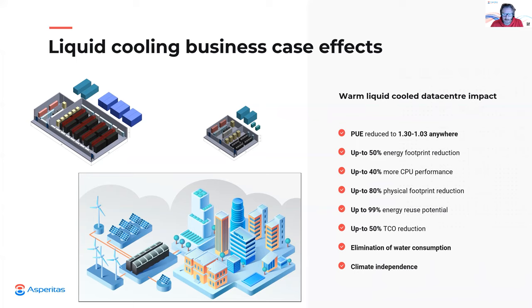as well, which can simultaneously allow much further energy reduction, resulting in reduced energy requirements for increased capacity for the facility. Especially in case of HPC applications, existing cold water circuits can be utilized to increase CPU performance. In general, cold plate and immersion technology will allow full CPU boost operations continuously. The physical footprint reduction is achieved by the IT consolidation, power savings, and more efficient free air cooling. The energy reuse potential is, of course, dependent on the chosen technology.